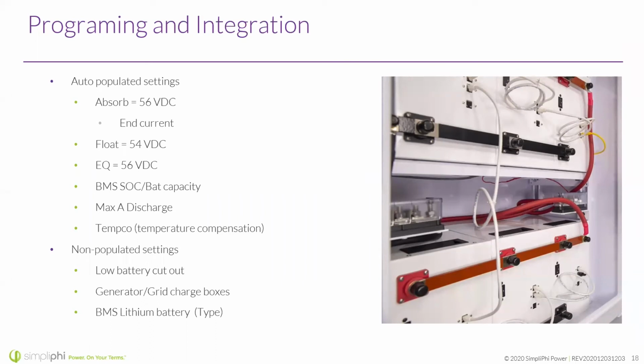So these are a bit interesting. Low battery cutout technically does not auto-populate. However, that's misleading. The low battery cutout now relies on state of charge, so it will never allow the battery to go below 0% state of charge. So that protection does automatically get programmed in.